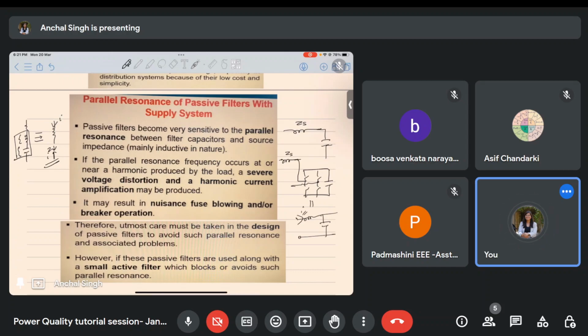Using these passive compensators—this C filter is again one type of passive filter, just a C—there are a lot of problems we have to tackle before implementing this kind of filter. In parallel resonance, the frequency occurs at or near the harmonic produced by the load. A severe voltage distortion or harmonic current amplification may be produced because of the reduction in impedance.